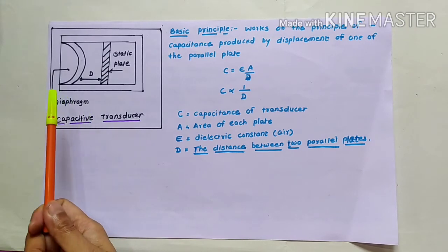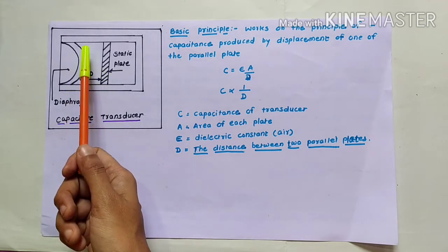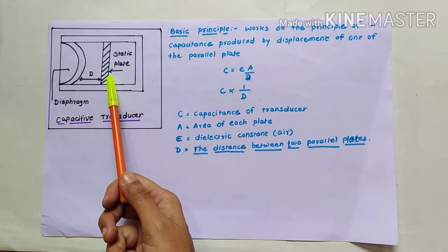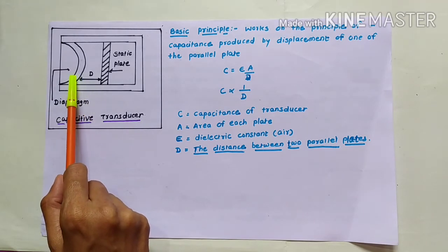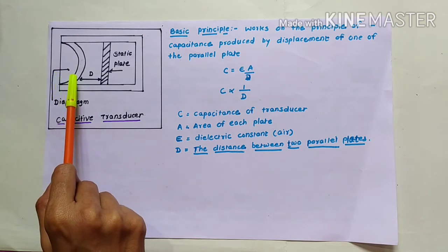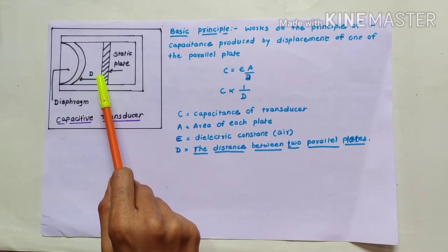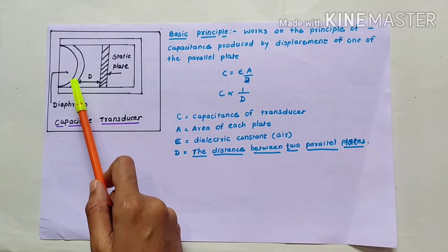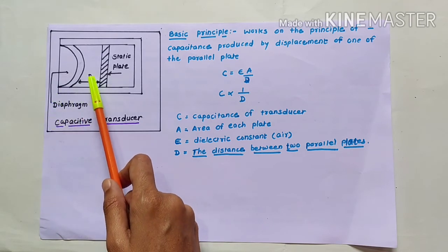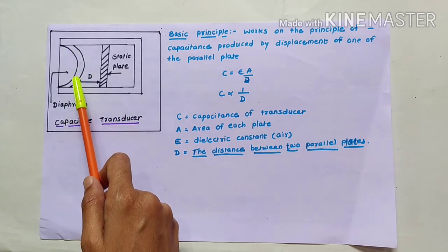Let us see the construction and principle of this capacitive transducer. It is constructed with the help of two parallel plates fixed in an insulating container. Out of these two plates, one plate is fixed — known as the static plate — and the other is a movable membrane known as the diaphragm. These two plates of an effective capacitor are separated by a dielectric, and air pressure which is to be measured is applied to the diaphragm.